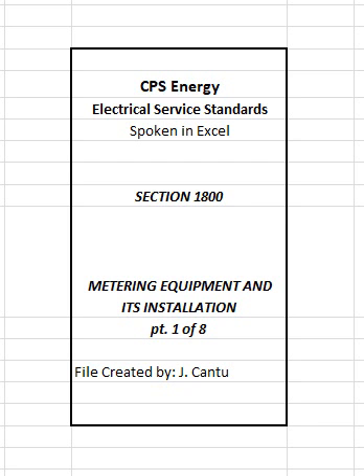A. Meter socket terminals are designed to accept either copper or aluminum conductors, but where aluminum conductors are installed, wire ends must be wire brush cleaned and have grit fill joint compound applied to them and the terminals before terminal screws are made tight. B. Customer must observe the terminal screw torque requirements that are labeled in each socket. Poor connections may be the result if the recommended torque is either reduced or exceeded.